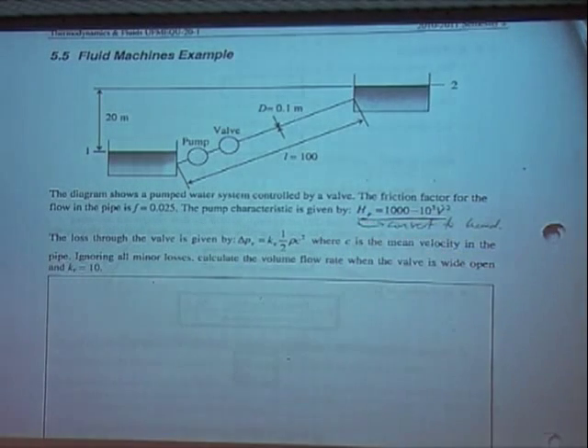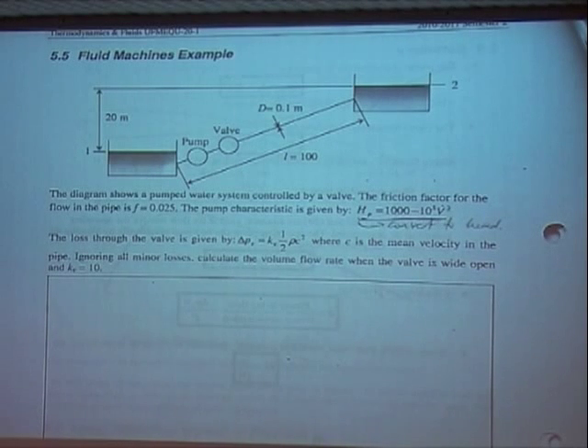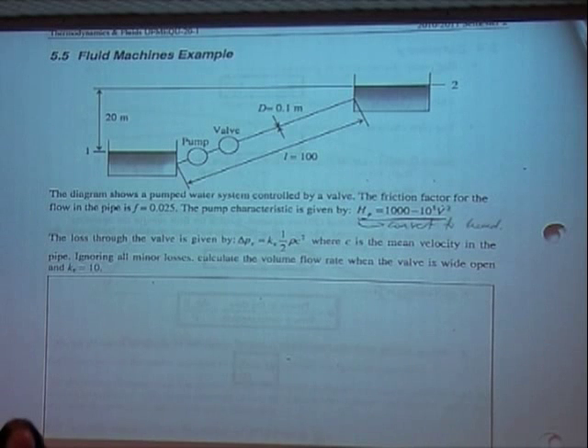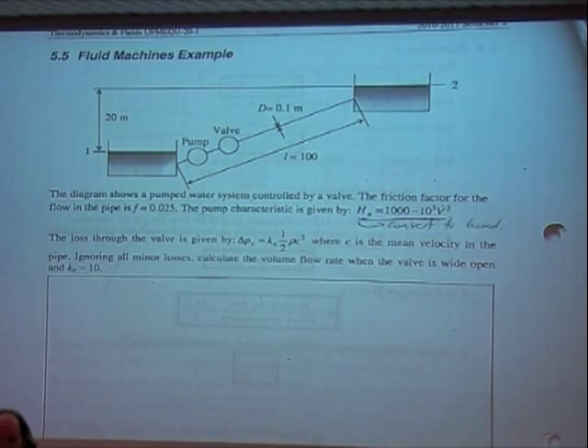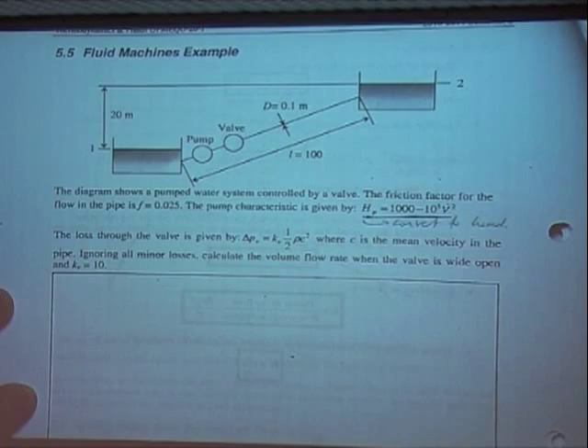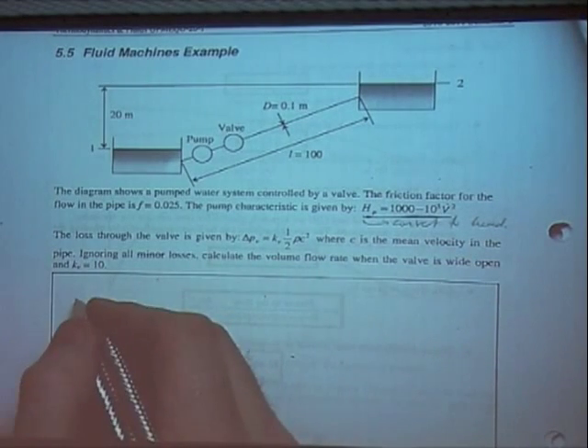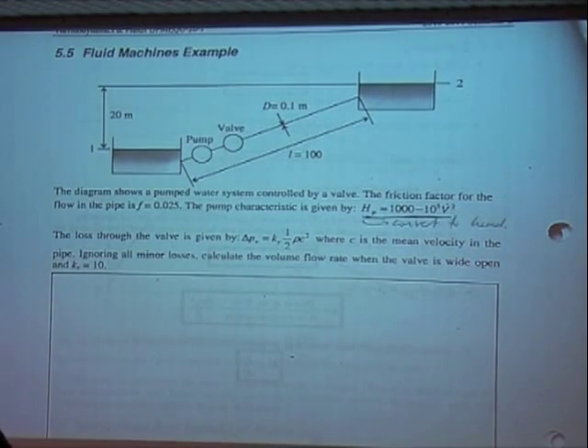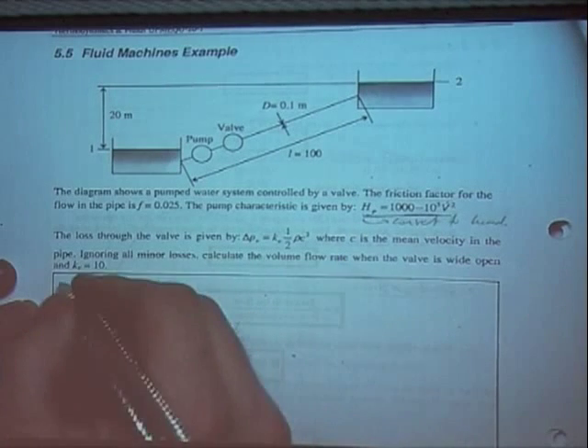Notice we've been given the pump characteristic, and it's been given in terms of head. Head is a distance, and to convert that to a pressure we need to multiply by rho times g. We're dealing with a system with water, and so we can write down the pump characteristic straight off.